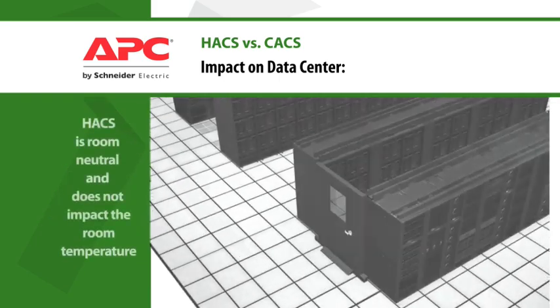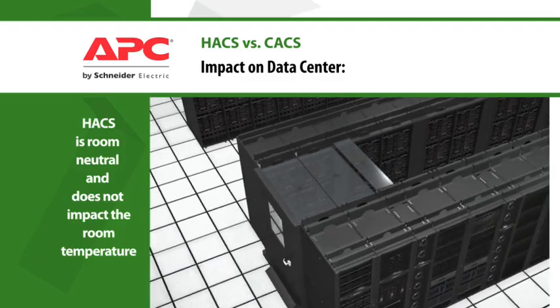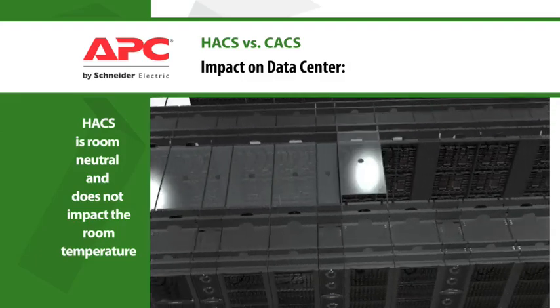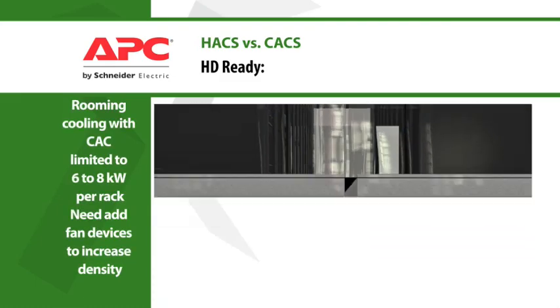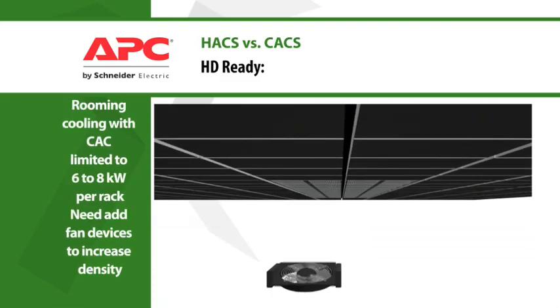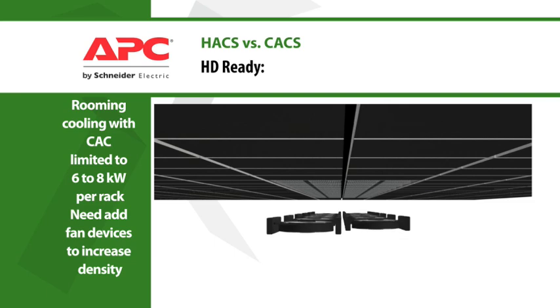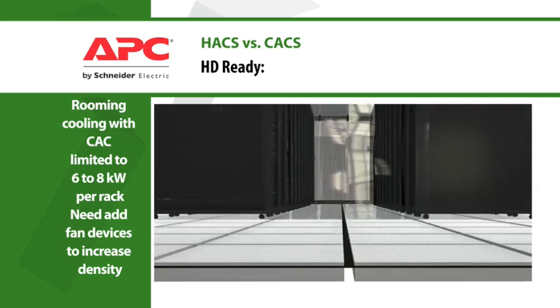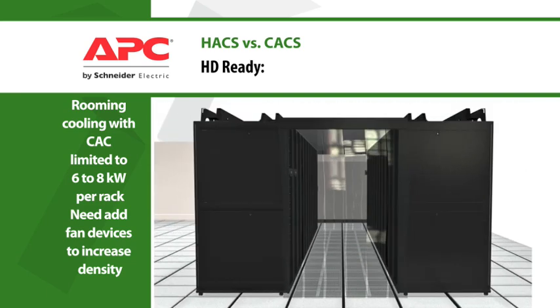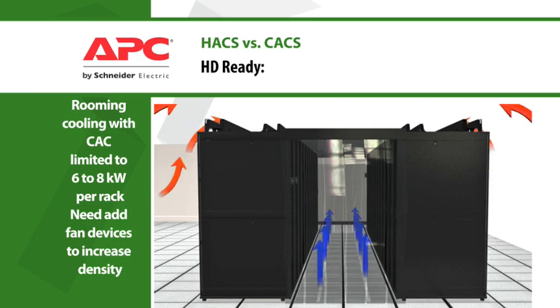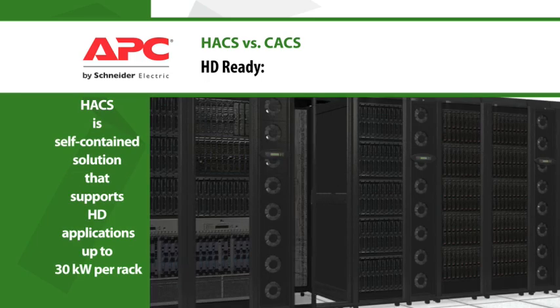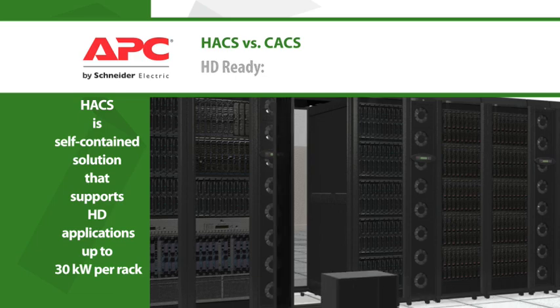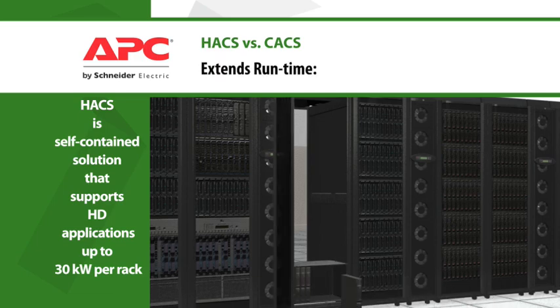The hot aisle containment system can easily be dropped in to any data center without impacting the data center environment. Typical raised floor systems only deliver enough cold air to support a maximum of six to eight kilowatts per rack. Higher densities require specialized design or the addition of fan devices for proper airflow. APC's in-row cooling solution in the hot aisle containment system supports densities of 30 kilowatts per rack and beyond.